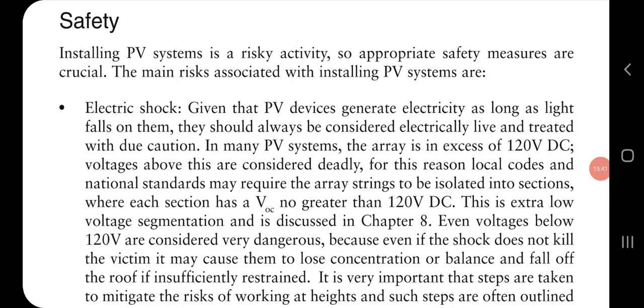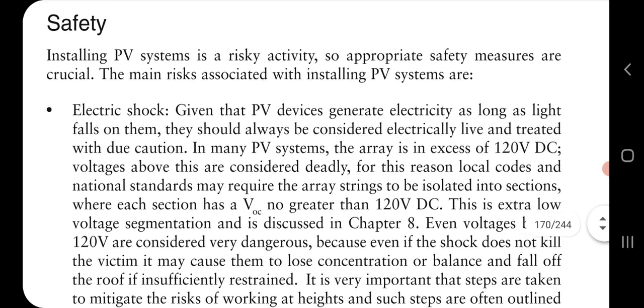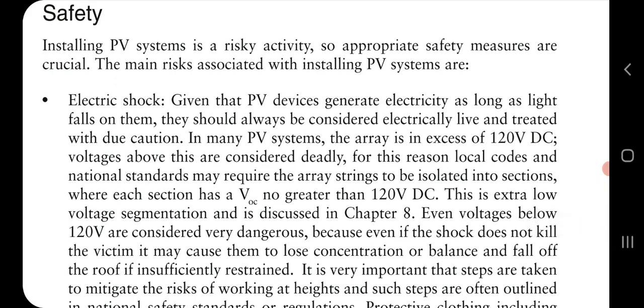Now let us discuss the safety procedures. Some safety procedures have to be followed while installing the PV system. The first is electric shock. Whenever you are installing a PV array, it is connected in series, so it produces a lot of voltage. A particular string or one module will be producing 120 volts DC supply. A 120 volt DC supply is a very large amount of voltage. It is very dangerous. Even below that it is very dangerous and can be fatal.